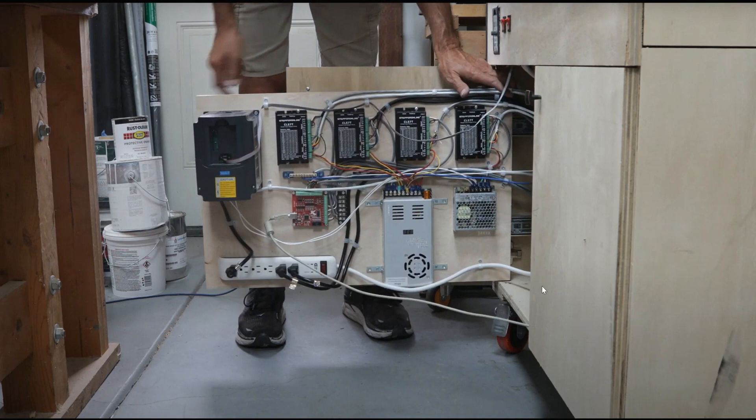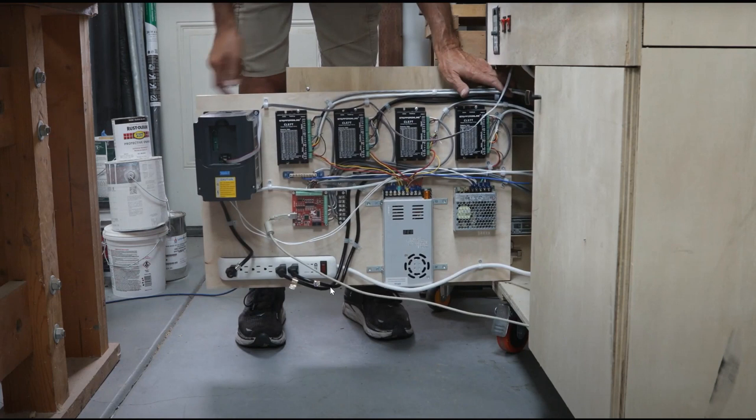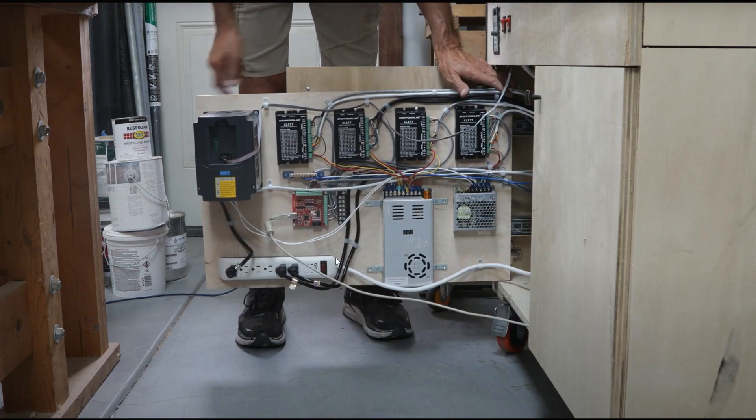I do not understand why one would put their life and family's life at risk doing this. Something else to point out here is that we see this used a lot - these surge protectors, power strips. Basically what these end users are doing, they're trying to split power. I understand that the issue is we see a VFD plugged into the same power strip as his electronics. So what do you think is going to happen when this VFD reaches its peak amp rating? It's going to naturally affect whatever breaker's attached to this surge protector. I doubt the individual actually looked to see if this surge protector was able to handle the amount of power draw.